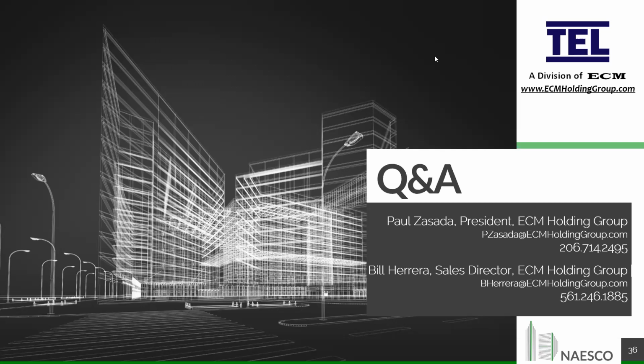As far as the BAS integration goes, we control the lab space. You'll draw a circle around that lab, and that needs to have one leader and one controller doing that. And then in our instance, we integrate from that lab to the BAS. So one point of connection to get all the information for everything that's going on in that lab: what the fume hoods are doing, what the general exhaust is doing, what the air change rates are. You read and write through that single point of connection to both collect data, and then you can change set points, et cetera. So it's a single point of connection, the BAS integration, and you let the lab controllers do their thing. And then you've got that little interface where you can direct some set points and collect data to make sure it's showing up on the front end computer.